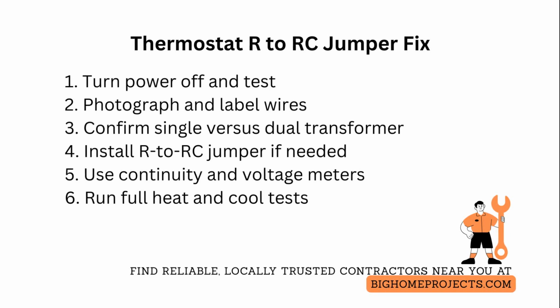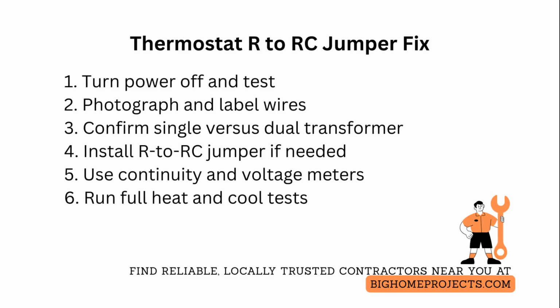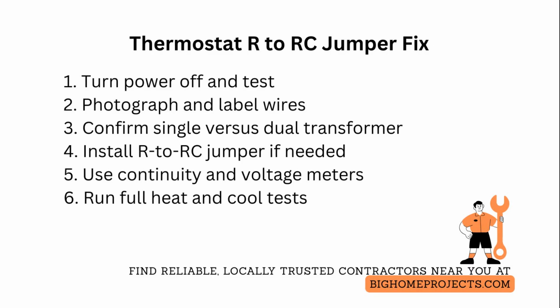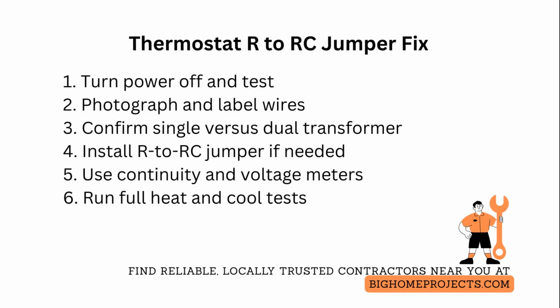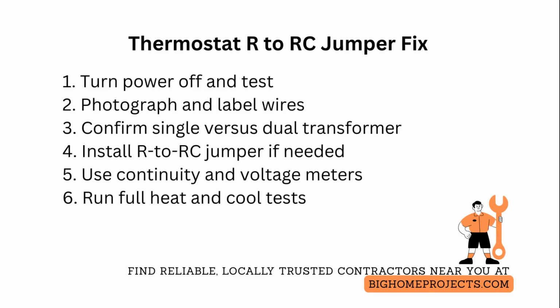Call for heat, confirm the furnace ignites and fan cycles, then call for cooling and confirm the compressor starts and the outside condenser engages. If you see the air handler fan running but the outside condenser does not, suspect a missing R to RC jumper or a failed contactor signal. Check for a blown fuse at the control board and verify the thermostat is set to the correct system type, heat pump versus conventional, so the control logic matches wiring.